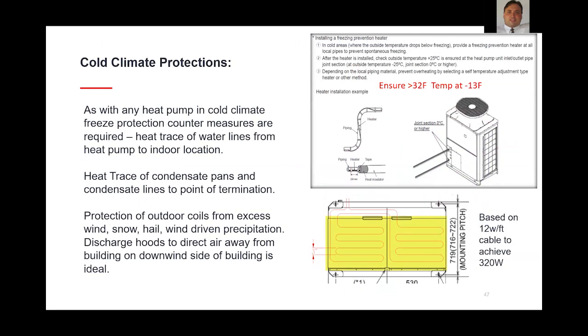All right, so cold climate protection. I know I'm getting a little bit tight on time, so I'm going to speed this up. I think we're getting near the end of this section, but cold climate protection is important. I mentioned this before, but the units need to be elevated above the snowdrift height. You want to have countermeasures to keep wind-driven precipitation and hail off of the coils. I talked about heat trace on the pans and the water lines being important. So just pay attention to that with manufacturer requirements.